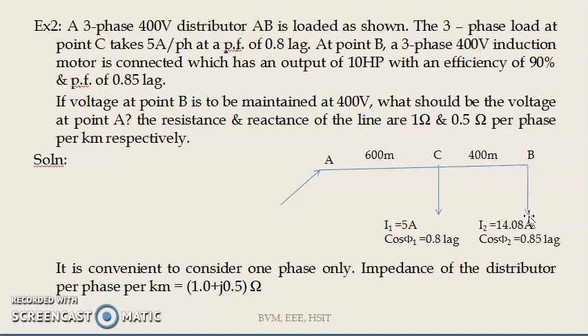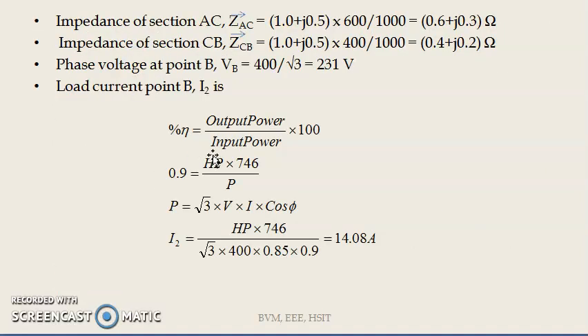What is ICB? It is I2. How did we get 14.08? Efficiency equals output power divided by input power times 100. Efficiency is 0.9 and output power is given in HP — convert to watts by multiplying by 746. Input power P equals root 3 times V times I times cos phi for three phase. So I2 equals (HP × 746) divided by (root 3 × 400 × 0.85 × 0.9), which gives 14.08 amps. This is your I2 load current, but it must be converted into a vector.